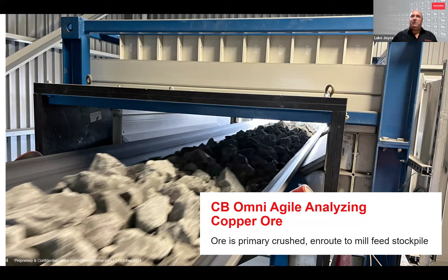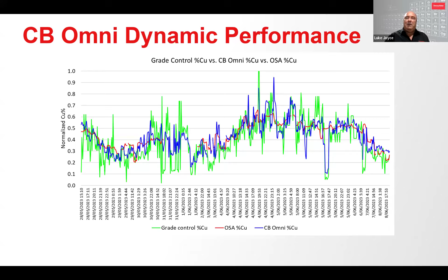At Red Chris, they were able to utilize existing upstream and downstream data sources to validate the CB Omni performance. They used upstream grade control and truck haulage data and downstream flotation feed slurry assays. They carefully accounted for the time delays associated with these different data sources to align the data and provide this graph, which gave them confidence that the analyzer was accurately reading the feed that they were sending into the process. So this demonstrates that using the 5 Ps and careful analyzer design and calibration methodology, it is possible to deliver online solutions that work, providing immediate value following installation and commissioning without the need for lengthy and costly on-site calibrations.